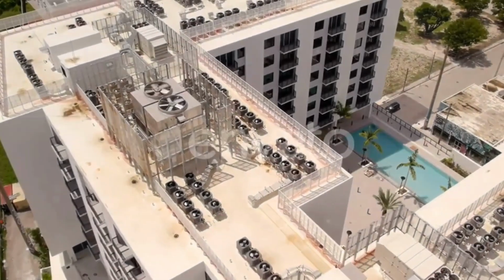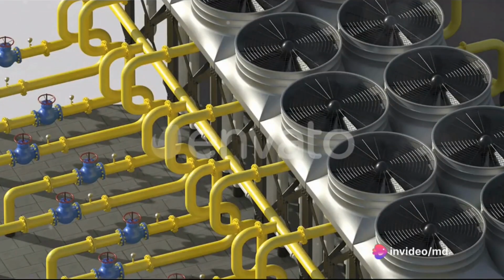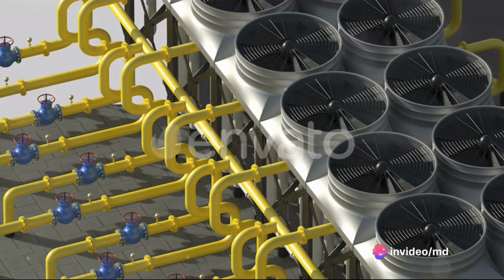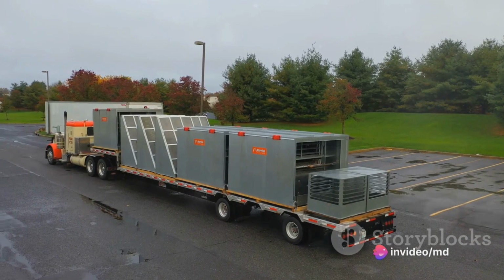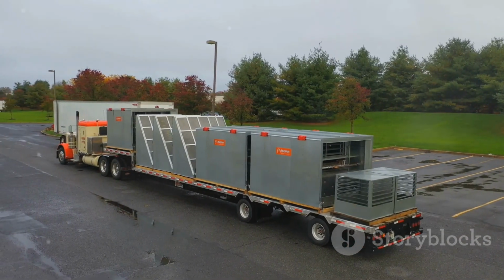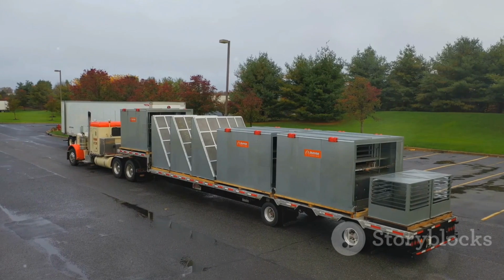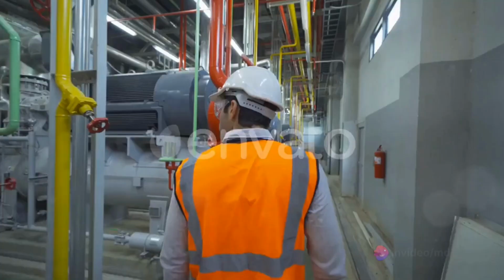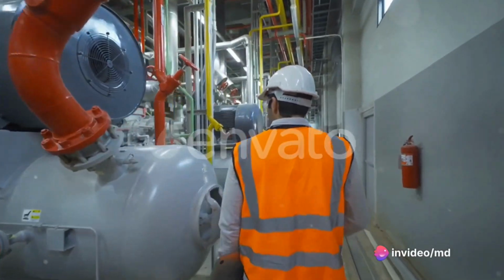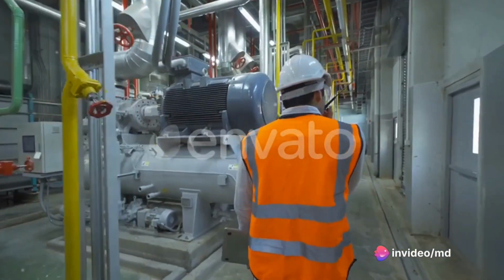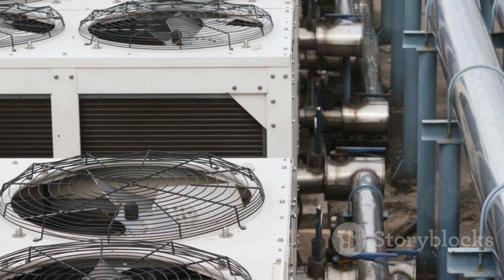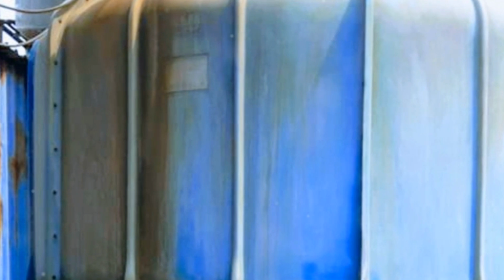Now, there are mainly two types of chillers: air-cooled chillers and water-cooled chillers. Air-cooled chillers, as the name suggests, use air to remove the heat. They are generally used in applications where the cooling required is less. On the other hand, water-cooled chillers utilize water to achieve the same result. Water-cooled chillers are more energy efficient than air-cooled chillers due to water's higher heat capacity. However, they require a separate cooling tower, which can increase the overall system's complexity and maintenance needs.